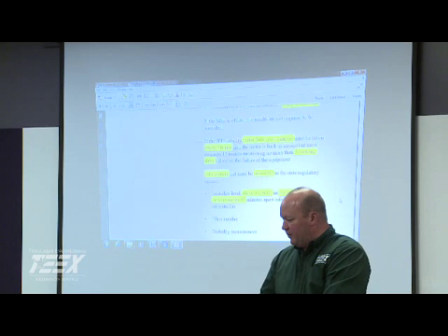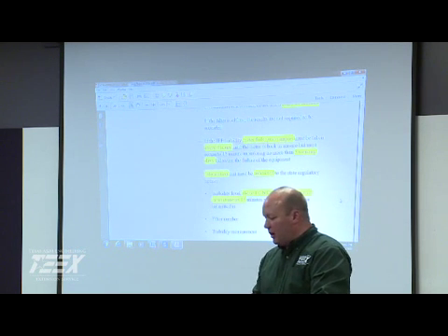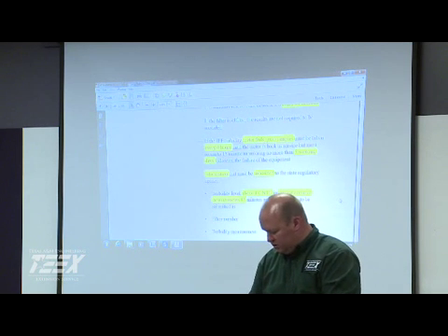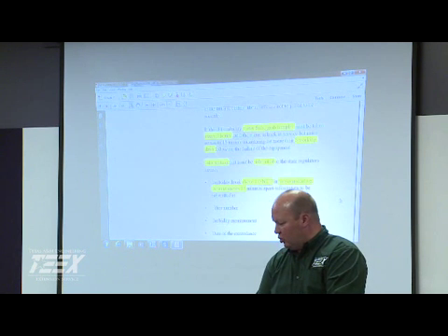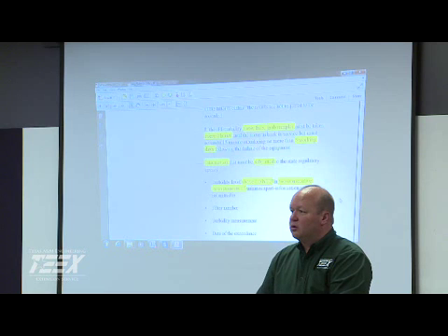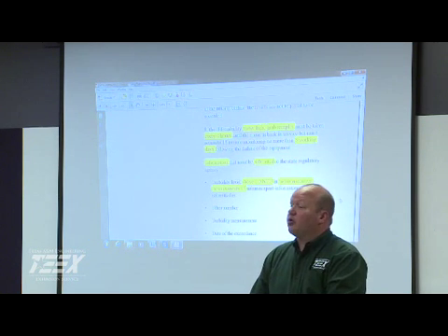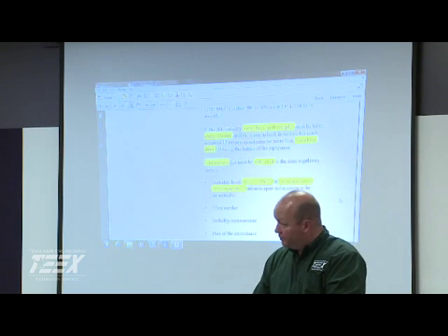If you do have a meter that fails, we talked about this on the exam, you've got to start doing your grabs every 4 hours. You've got 5 days to get it back in business, 5 working days, not calendar days. So it gives you a little bit of time to get something ordered or sent off. Actually, we go with calendar days. Do you now? Yeah, because on the weekends we consider that part of the time the plant's operating, so it's 5 days.